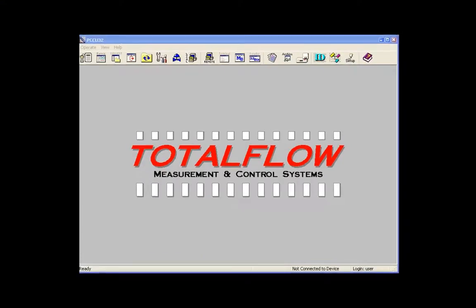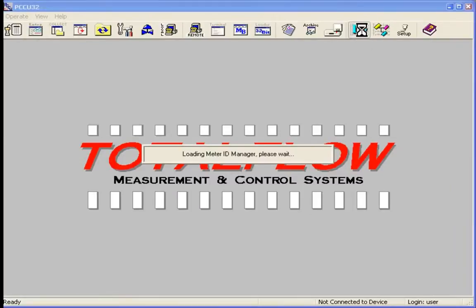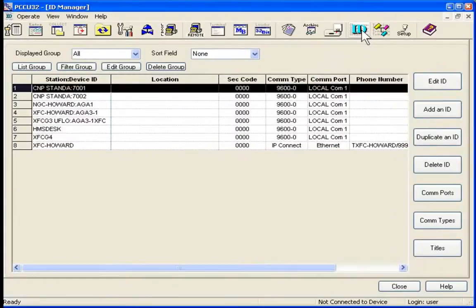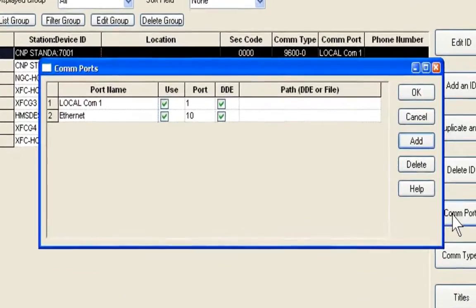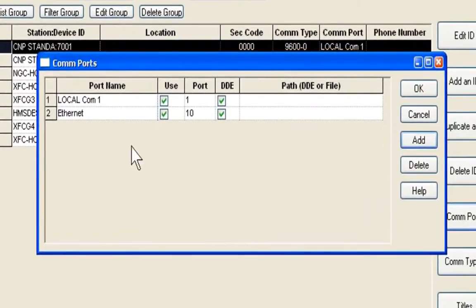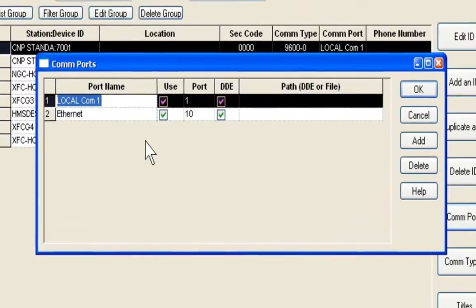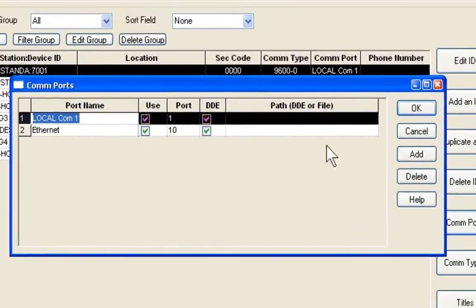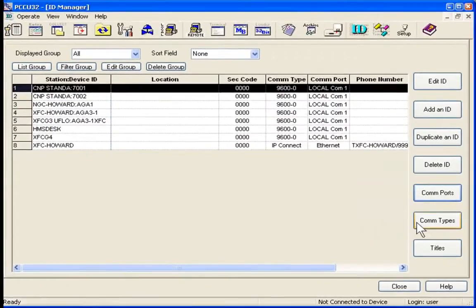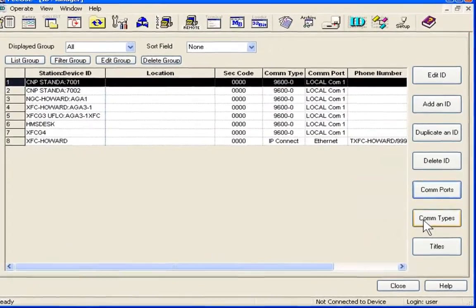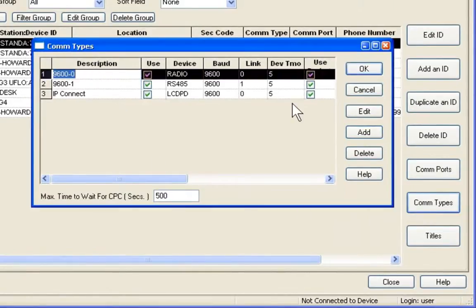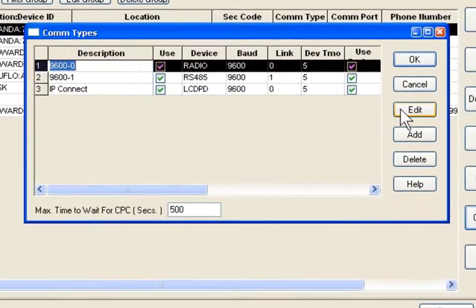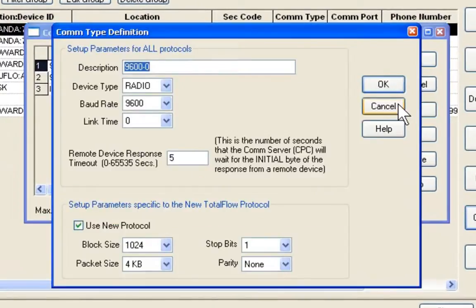For us to be able to use remote communications software in PCCU, we must first establish a G4 meter ID in the ID manager. To do this we select ID manager, we establish our comm port, make the settings you see here, say OK. Next we'll establish our comm type. If we don't have one set, we'll enter one. In this case we'll just edit the one I have here. 9600 zero.